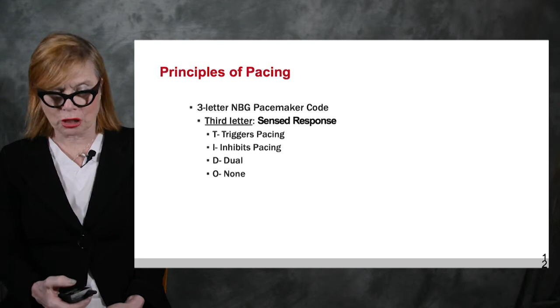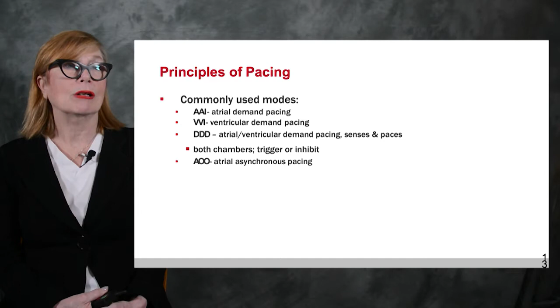So commonly used modes, AAI, that means the atria is paced, the atria is sensed, and if the patient has his own P wave, then we will inhibit the firing from the pacemaker. So pace, sense, response. VVI, can you guess? Absolutely. Ventricular paced, ventricular sensed, and inhibited when the patient has his own endogenous QRS. DDD, which is an atrioventricular pacemaker, demand, sensed, and inhibited and triggered. So that's very important. And last, AOO, atrial asynchronous pacing, or DOO, dual chamber asynchronous pacing. Okay, so let's start.